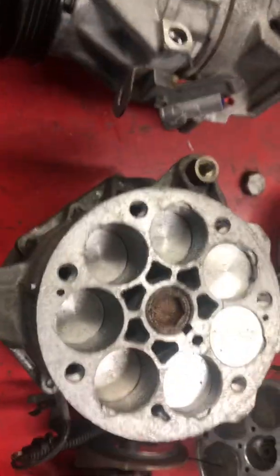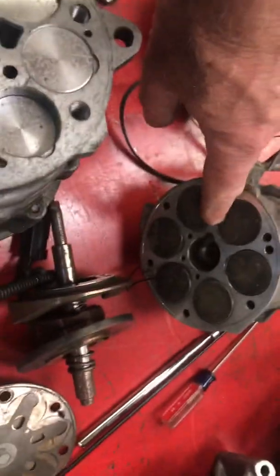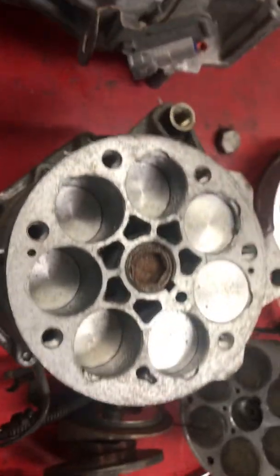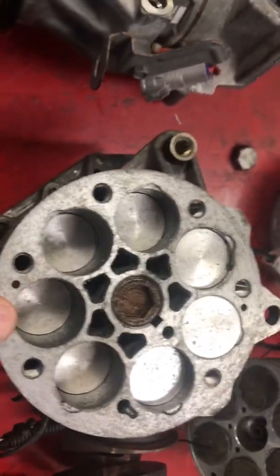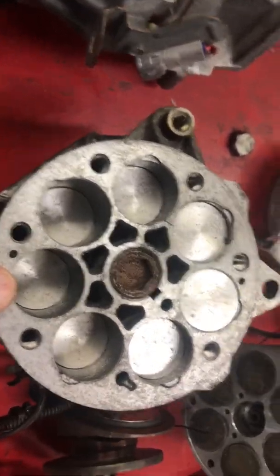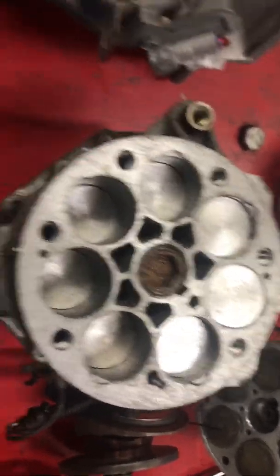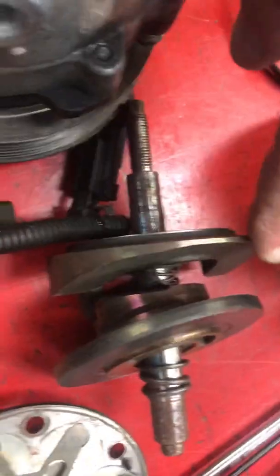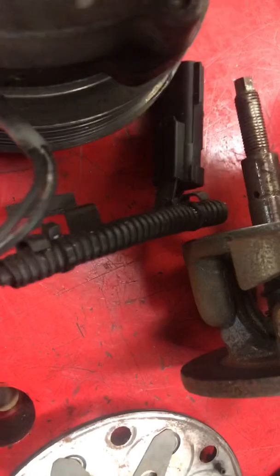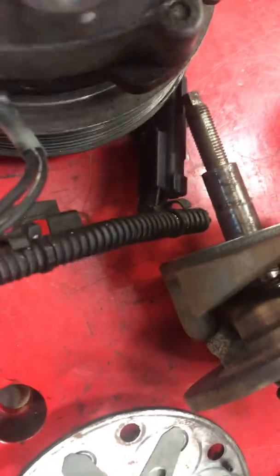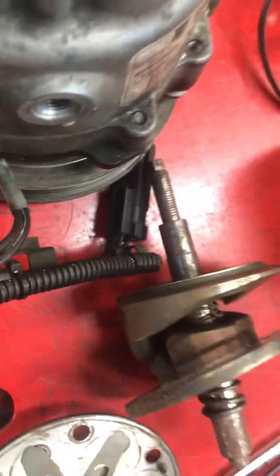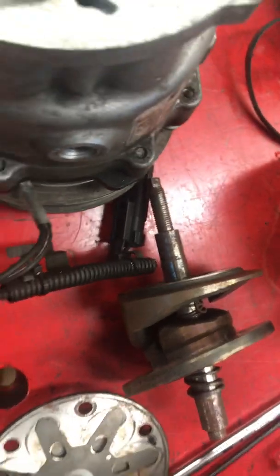So we're talking about the swashplate and what's going on inside. This is a swashplate compressor, 6-cylinder, and you can see this is a fixed swashplate displacement, and the pistons go up and down, move the refrigerant around. This is kind of the device where you can see the swashplate can move to a different angle, and those pistons will ride on that swashplate. That's how we change the displacement.